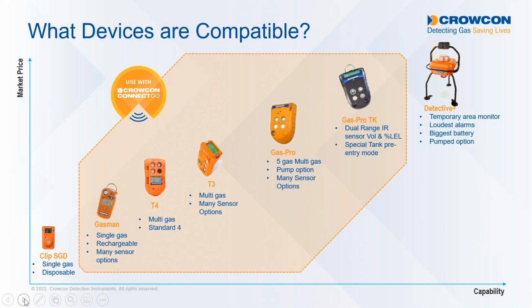Then we've got the Gas Pro TK, a very specialized device ideal for tank applications, where entering the tank and monitoring the tank's volume of gas and LEL gas is really important and safety critical. It uses a dual range IR sensor, which measures percent volume as well as percent LEL flammable gas in any area. It can be pumped using an integrated pump, and can also be used as a standalone safety device when not in tank check mode.